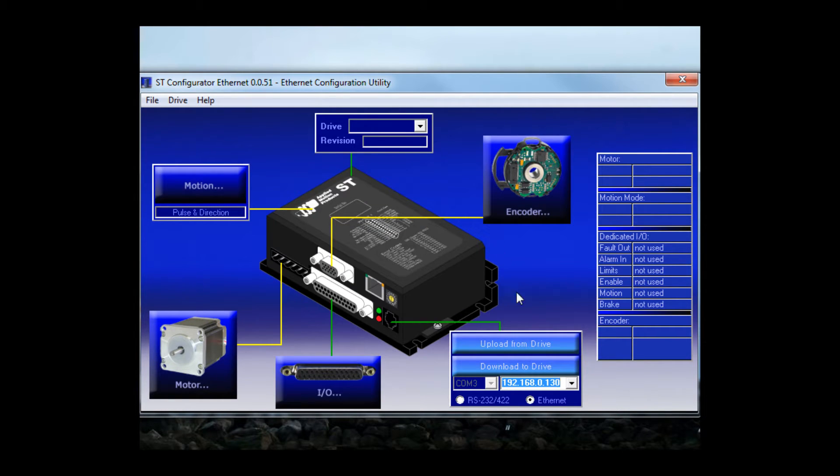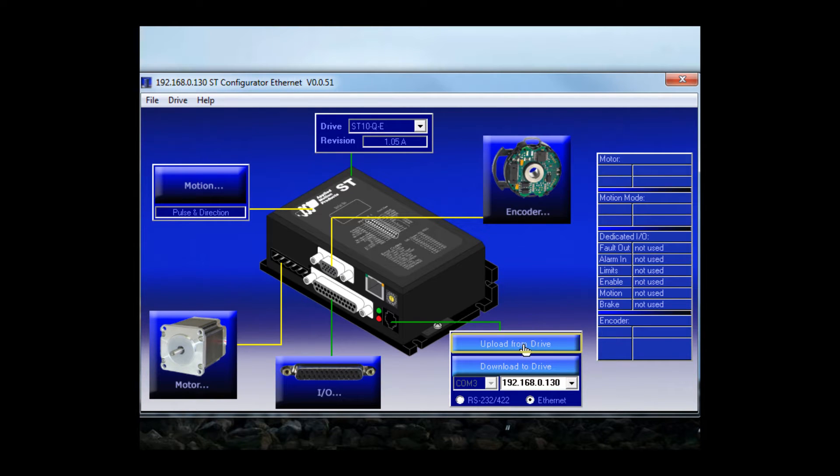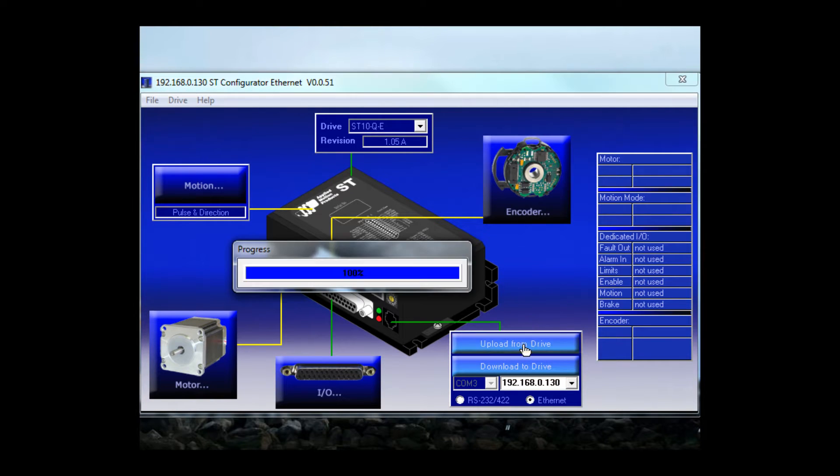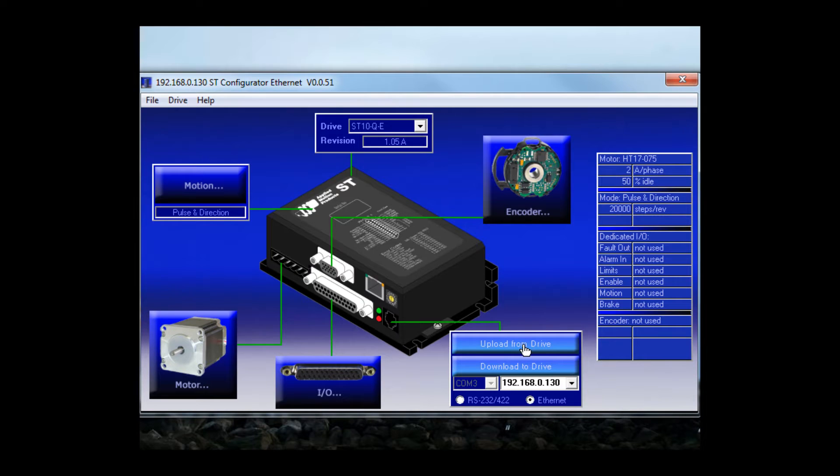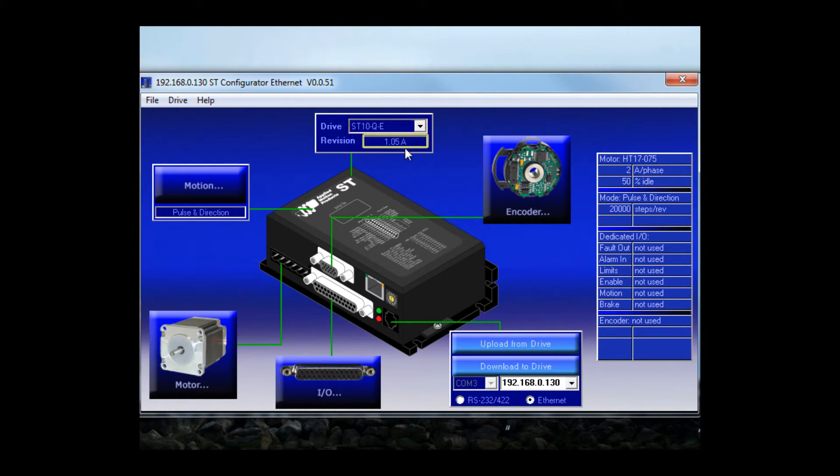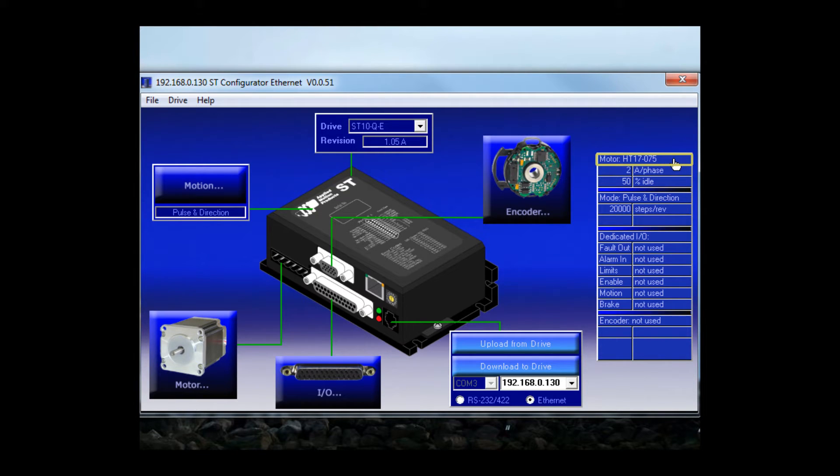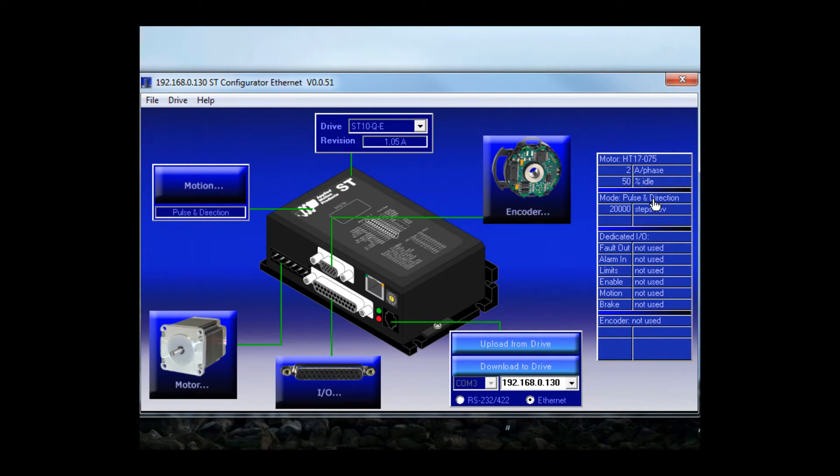Now let's hit the upload button and see what's in the drive now. I see that our drive is an ST10Q-E with firmware version 1.05A. The motor is an HT17075. That doesn't match the motor I'm using. I also see that the control mode is set for pulse and direction. We'll need to change that to Q programming.